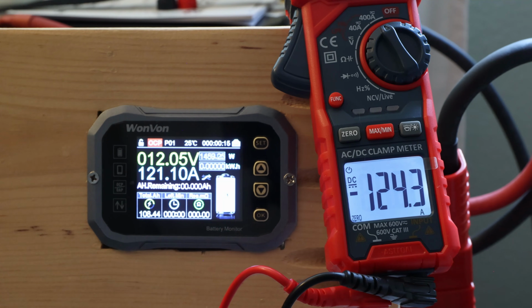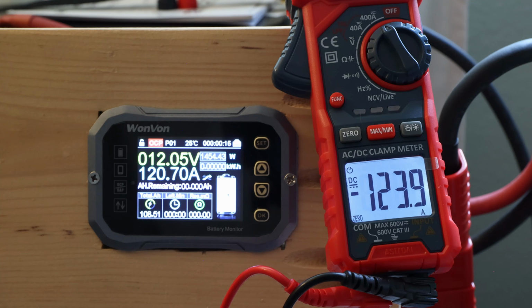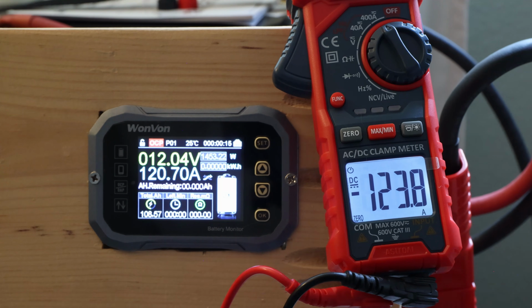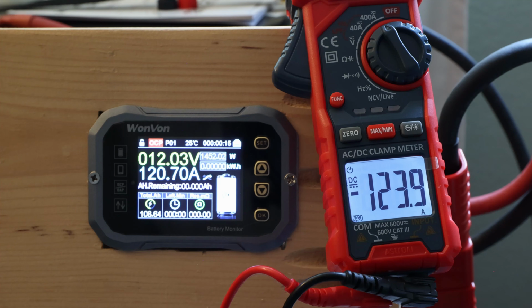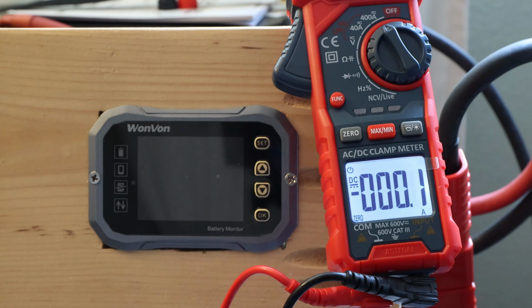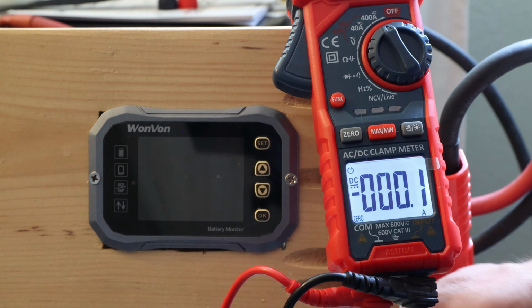Okay, you can see everything below where it works, no problem. What the threshold is, it just stops. Can't say exactly, but it looks like up to 200 amp and up to 5 seconds is where it stops and throws an error and needs time to come back. All right, good, that's the high discharge test. So they're as advertised, the BMS is actually doing what it's supposed to do, so that's good to see.